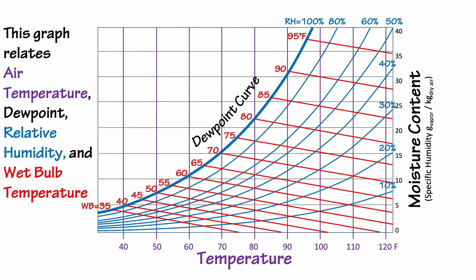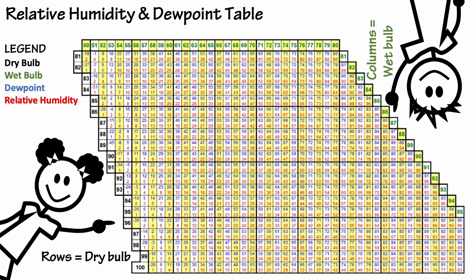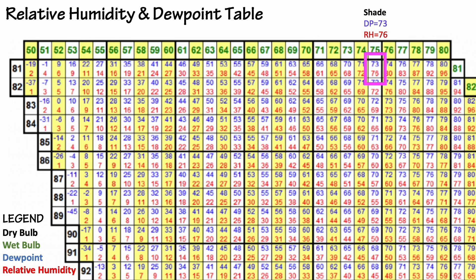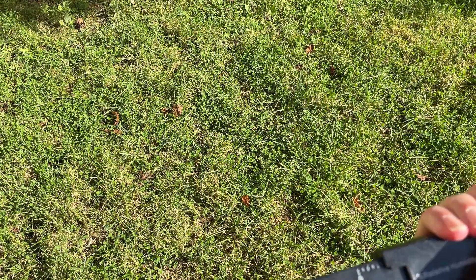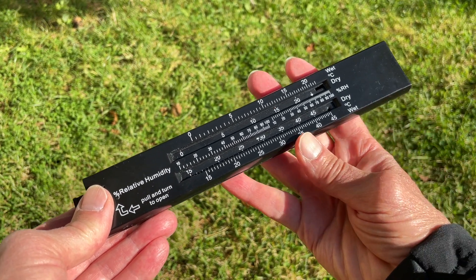Because there's so much going on in this graph, some people prefer to use a table of values for wet bulb and dry bulb. On the table, the dry bulb values are the rows and the wet bulb values are the columns. At our first site in the shade, dry bulb is 81 and wet bulb is 75, so relative humidity is 76% and dew point is 73°F. In the parking lot, dry bulb is 86 and wet bulb is 77, so relative humidity is 67% and dew point is 73°F. And on the grass, dry bulb is 84 and wet bulb is 76, giving relative humidity of 69% and dew point of 73°F. Some sling psychrometers even have a little humidity slide rule printed on the thermometer case.